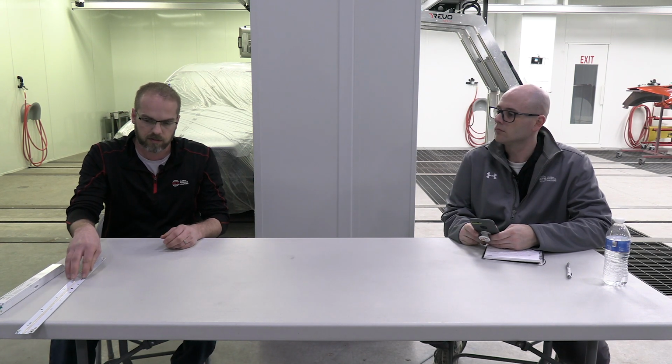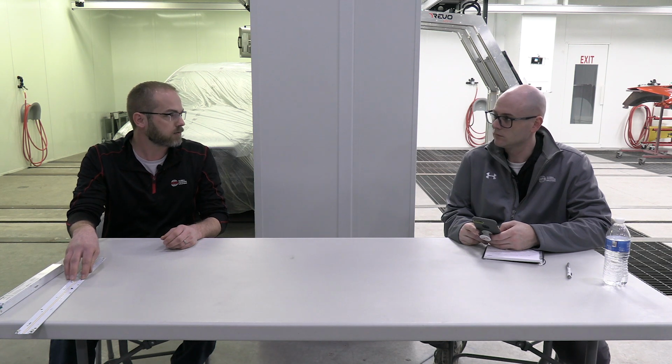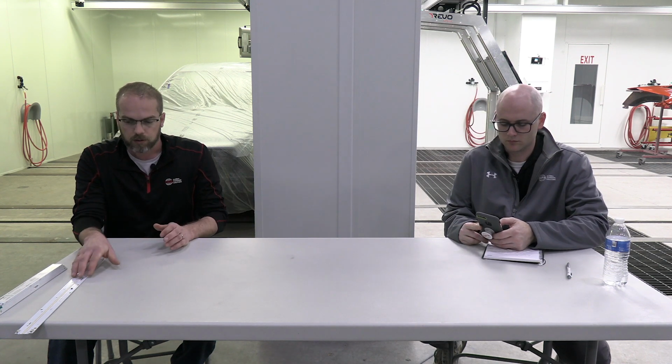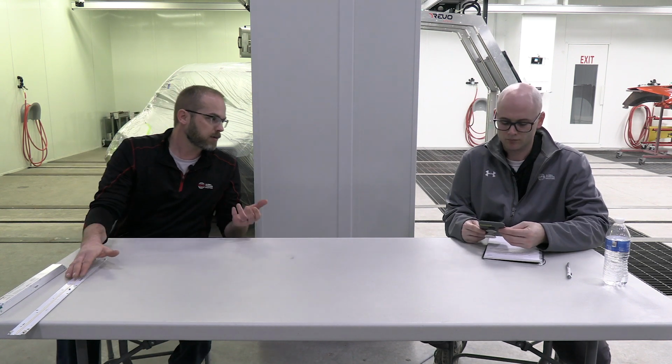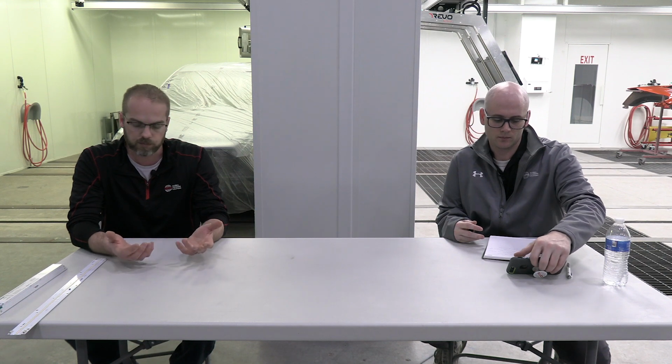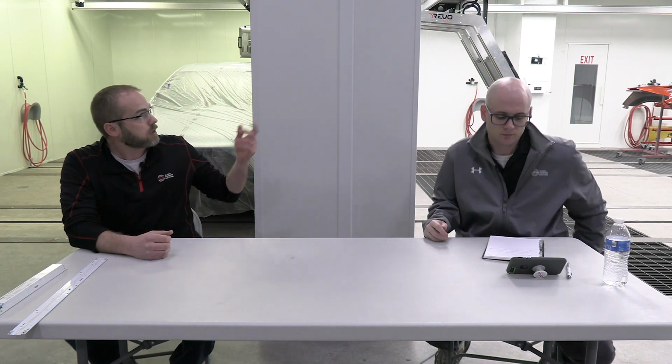The efficiency of the LEDs is higher than fluorescent. When they first came out, even 4 or 5 years ago, they were kind of on parity. But today, you will get more lumens per watt on an LED fixture. So that's one of the primary benefits of the LEDs, that you get a much more efficient fixture. In this case, our LED tubes draw approximately 17 watts apiece.